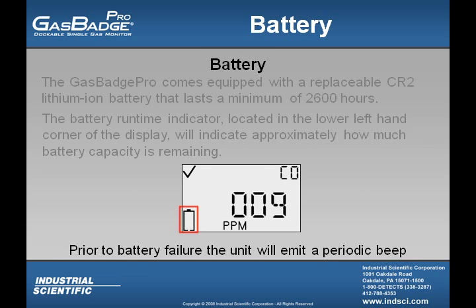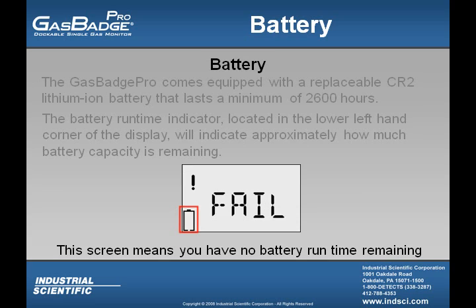Once the battery goes blank, the instrument will emit a periodic beep, letting the user know they need to replace the battery. If the user continues to use the GasBadge Pro to the point where the battery doesn't have enough life left, the display will show an exclamation point and also the word fail, letting them know that the GasBadge Pro's battery has failed. If this condition occurs, the battery must be replaced.